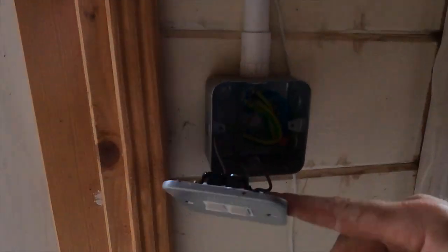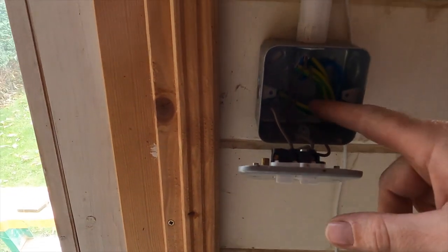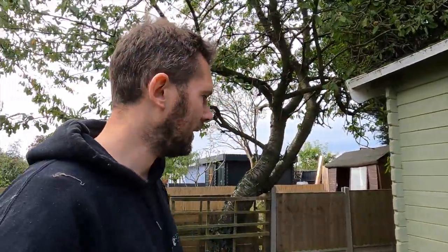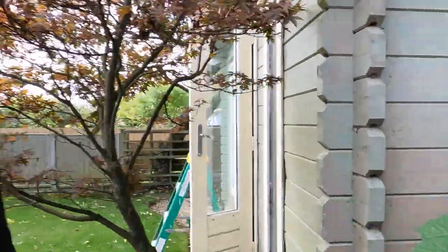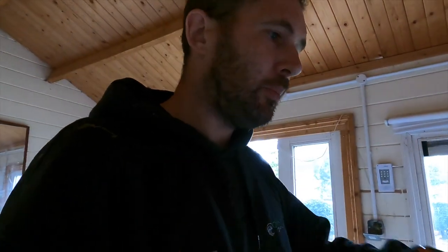It's the same issue throughout the actual house — all the sockets outside have nice metallic fittings, they're not cheap either, but none of them are actually earthed. Not one. I find that bizarre. So just double-checking the outside of the office now, making sure there aren't any sneaky power points or other lights. Because if you miss one, that might be the one that burns the place down. I'll get everything built back up and then we'll jump on to doing our live testing.